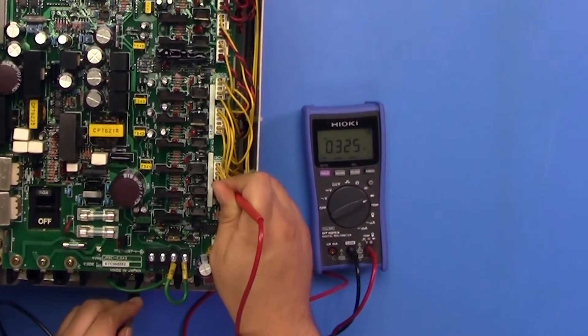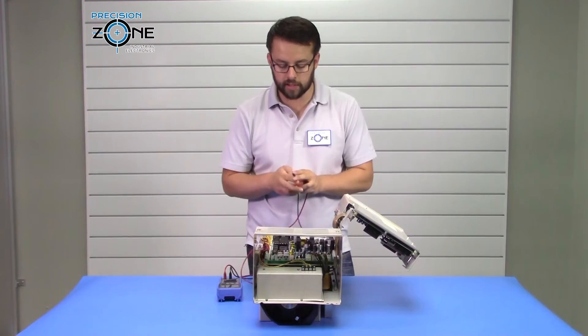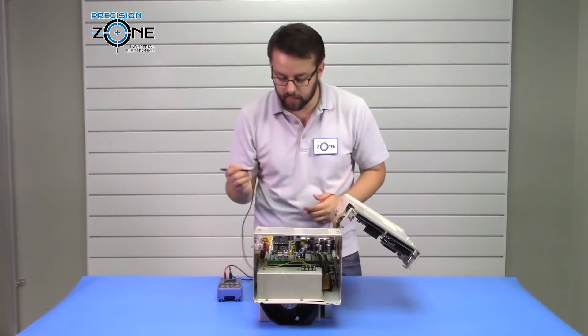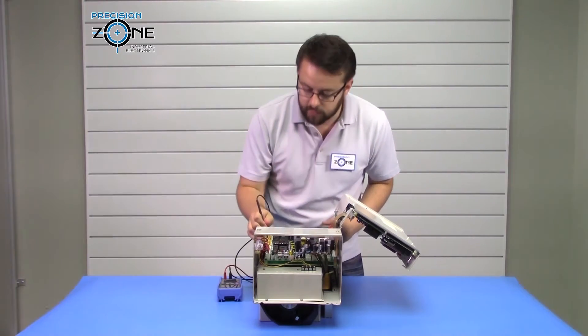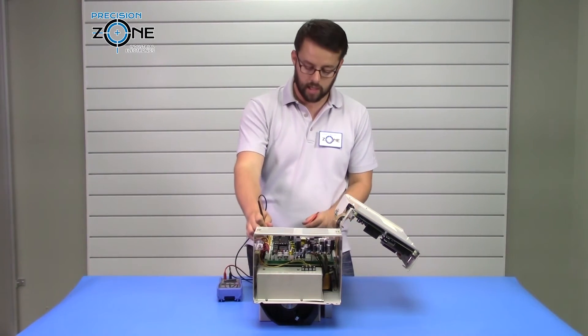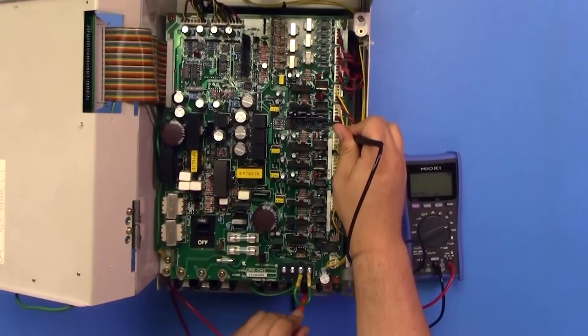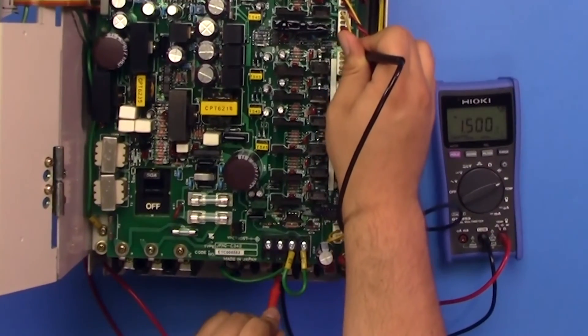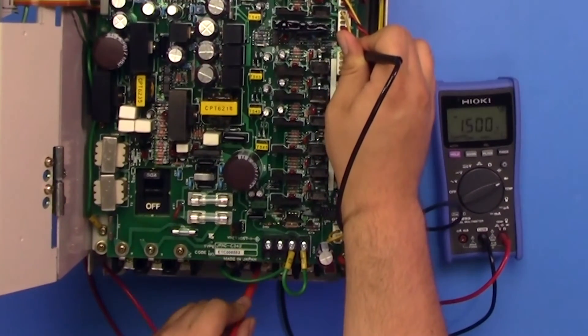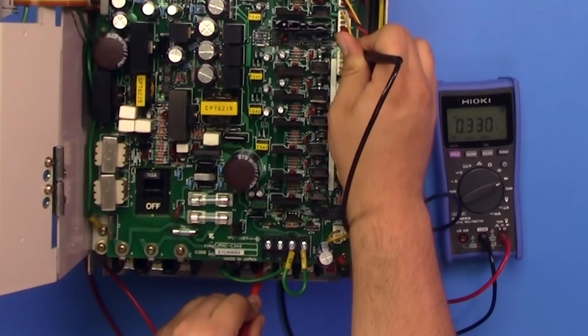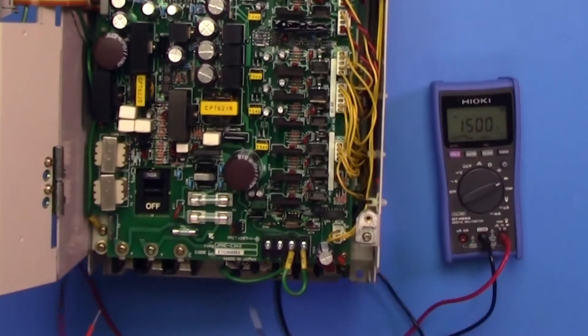Now you're going to switch your leads. Get the negative side of the digital multimeter and connect that to the positive side of the DC bus at this pin. You're going to check UVW, which should be about 0.33 volts. So that is normal.